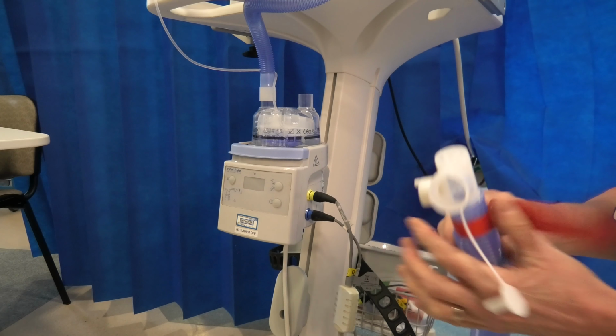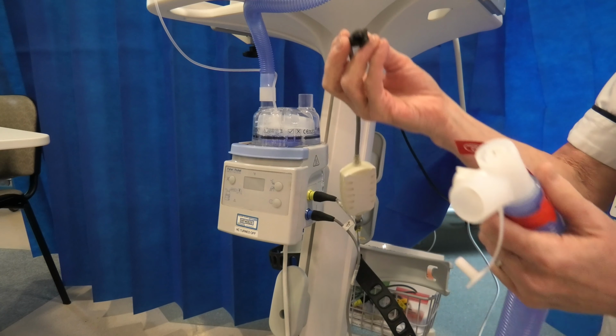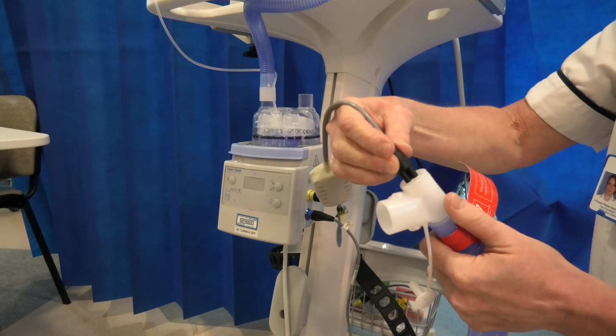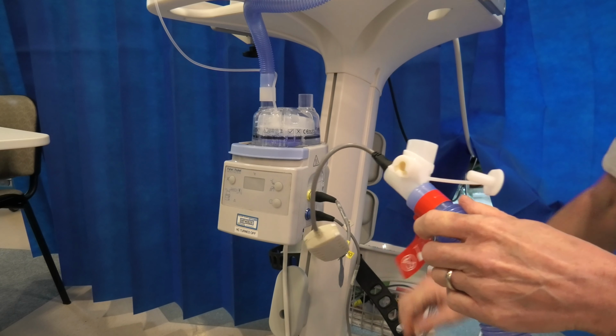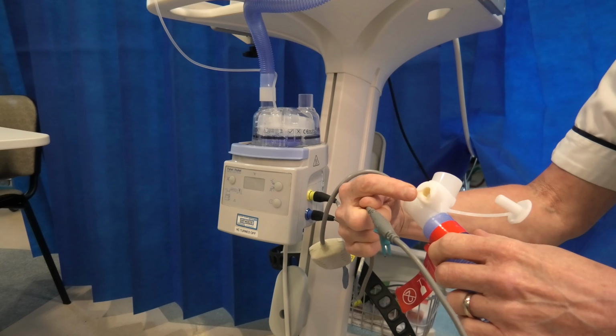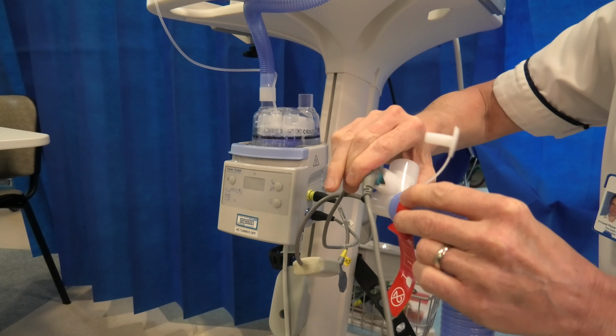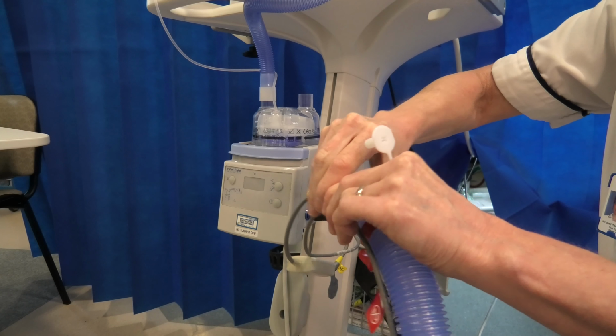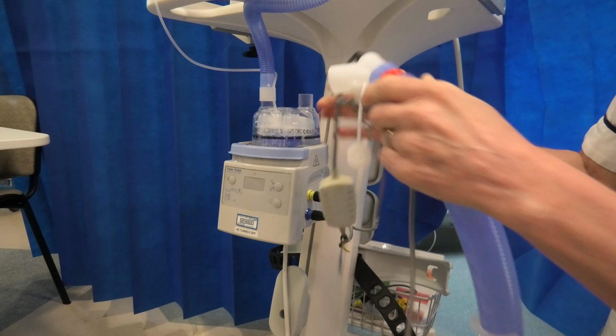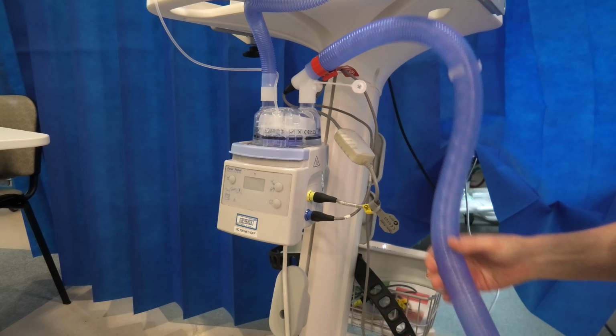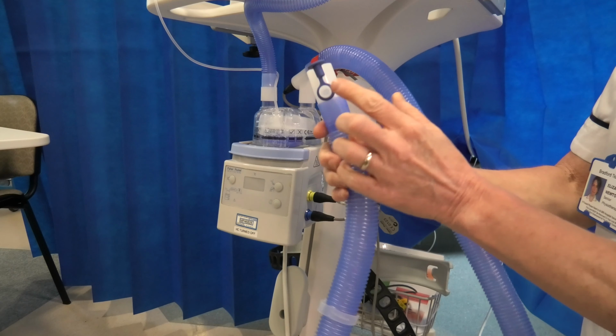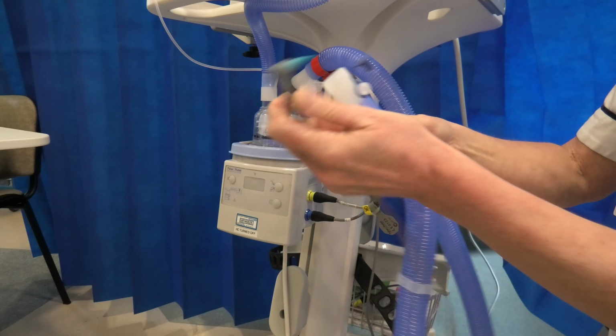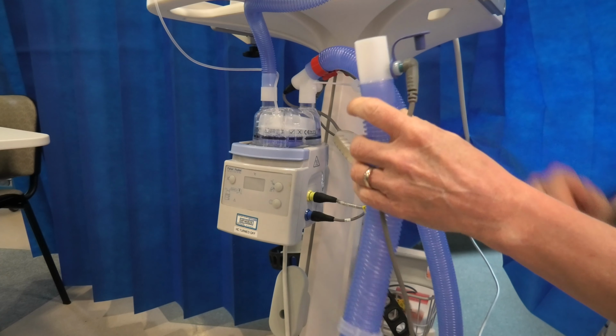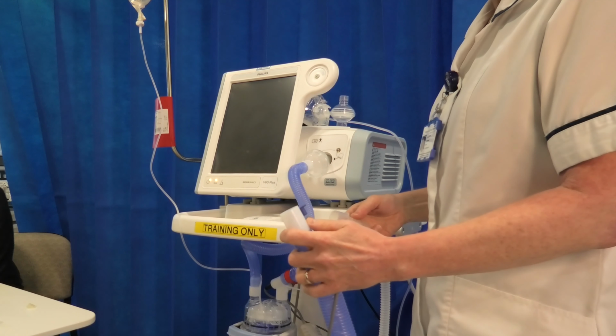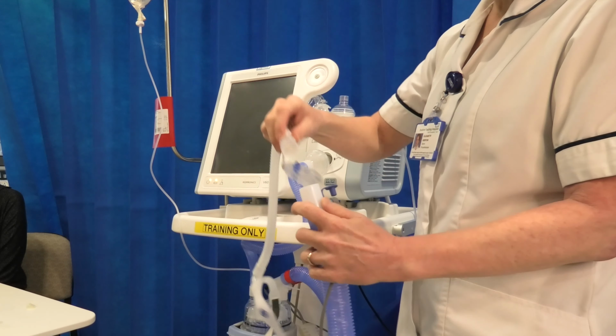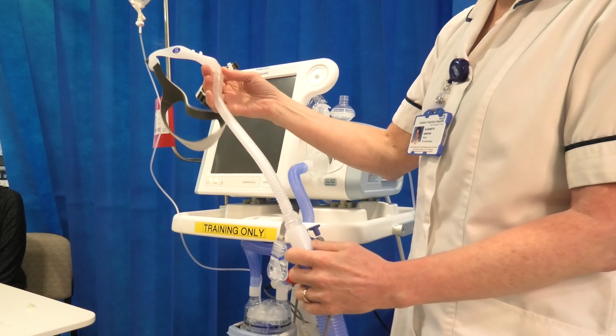So if I just show you, we have the yellow wire here, which has the clover leaf attached. That goes in to the clover leaf end. And then the start of the blue wire has got a triangular attachment, which slots in this end. Give that a good shove to get it in. Then this end of the circuit fits on the humidifier. On the other end of the circuit, we have another port. So the other end of the blue wire will go in there, and that's the temperature sensor at the patient end. If I'm going to use this wet circuit for nasal high flow, all I have to do is attach my specialist nasal cannula onto the end and attach that to my patient.